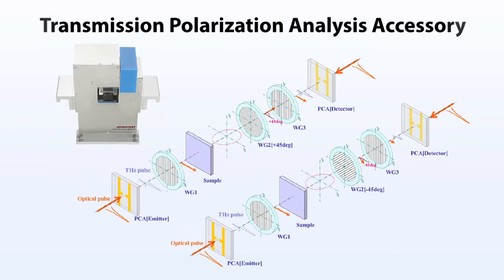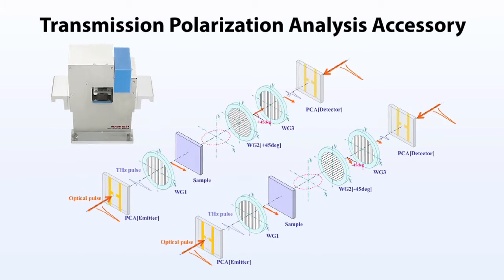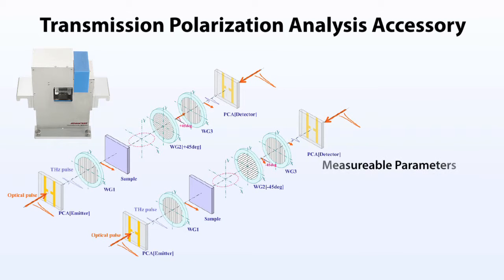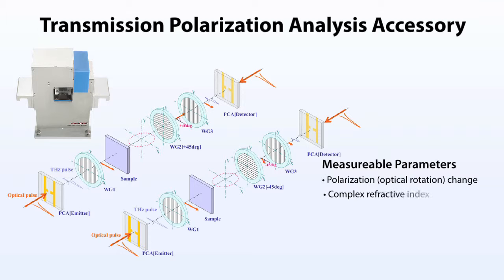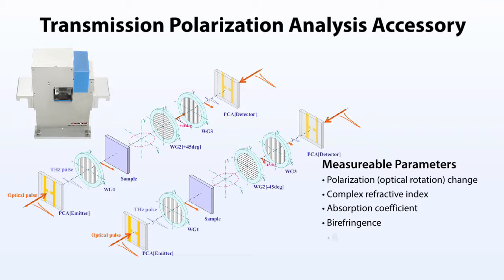The transmission polarization accessory uses a series of three linear polarizers to read out optical rotation angles. The first and third polarizers are set to the polarization plane of the initial terahertz pulse. Optical rotation is measured by combining two sets of data obtained with plus 45 degree and minus 45 degree settings of the second polarizer.